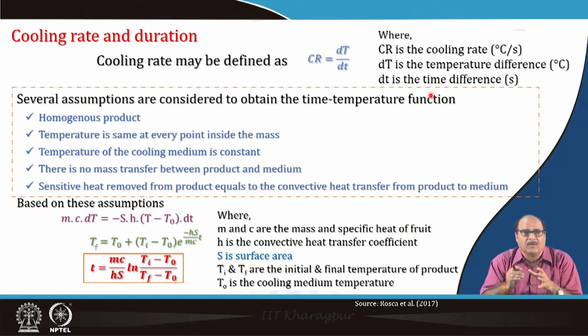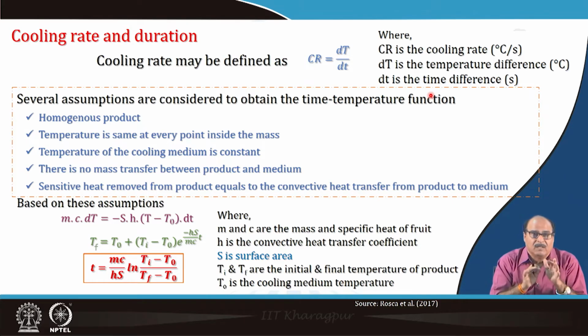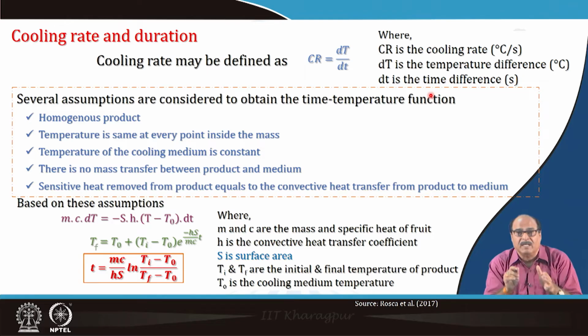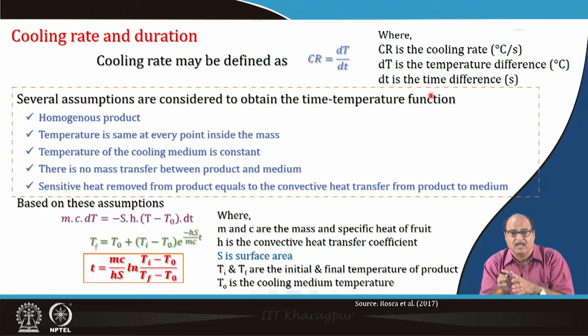In this calculation several assumptions are considered to obtain the time-temperature function: the product is homogeneous and homogeneously filled, temperature is the same at every point inside the product, the temperature of the cooling medium is constant, there is no mass transfer between the product and the medium, and sensible heat removed from the product equals the convective heat transfer from the product to the medium.